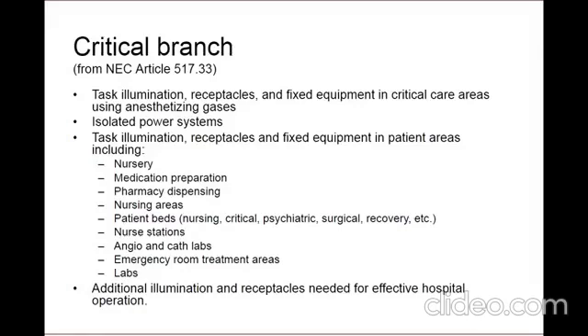The critical branch also lists items that are required to be on this branch. However, the code leaves this one a little more open to put items other than those that are just called out in the code, as long as they're required for effective hospital operation and not already listed as being required on a different branch. These items include all of the following: task illumination, receptacles, and fixed equipment in critical care areas, isolated power systems, so the systems that Rob was just talking about, illumination, receptacles, and fixed equipment in patient care areas, including the list you see here. I'm not going to read that to you.